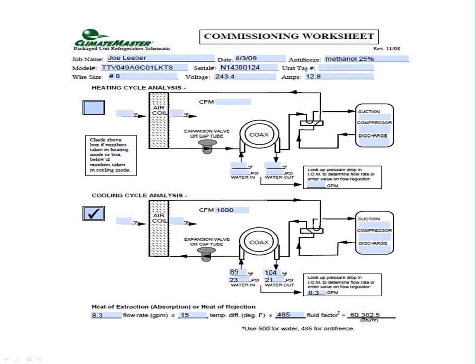Our next example here is a 2-speed 049. This one has a little bit of a heavy methanol solution. This one is checked in cooling, so let's take a look here. We have an entering water or fluid temperature of 89 degrees, and it's exiting at 104. So we're getting about a 15-degree temperature rise. We have a PSI entering of 23, and it's exiting at 21.